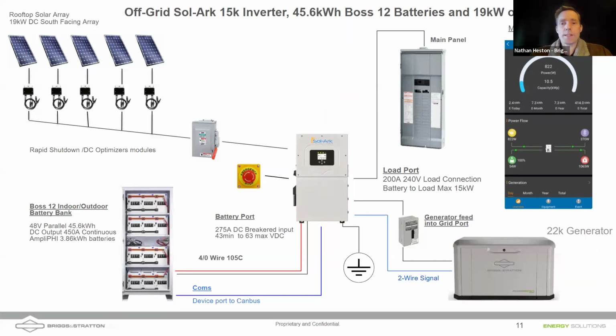And now we're looking at a system where we've actually integrated a generator. So very much the same. We're showing different rapid shutdown modules there. But a similar setup, we're showing a different type of our batteries. That's our Boss 12 battery cabinet. That's much bigger than that 20 kilowatt hour stack, which is a little over two times as big.